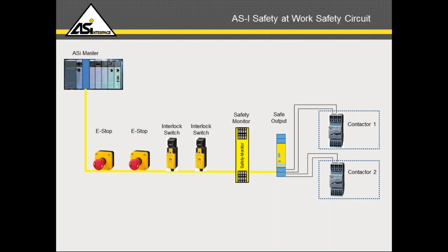The result is that diagnostics and monitoring are accomplished pretty easily. Which e-stop is activated, the status of the interlocks, the status of the contactors, all that's handled over the single AS-i network cable, enabling much smoother assembly, commissioning, startup, and maintenance like we talked about. In addition, the outputs can now be controlled independently. Remember I said that the hardwired topology really lends itself to a very stiff and inflexible application. Now contactor 1 here doesn't necessarily have to be turned off when contactor number 2 is. That allows for a lot more flexibility in the control scheme. This allows us to do zone control, for instance, and that's real easy to accomplish using the AS-i Safe technology.